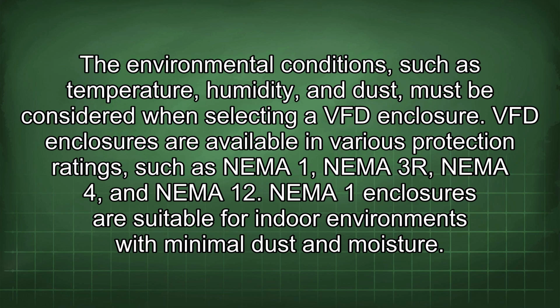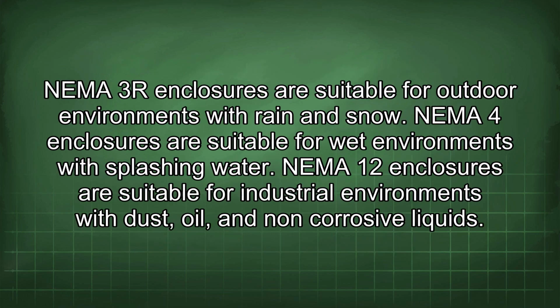VFD enclosures are available in various protection ratings such as NEMA 1, NEMA 3R, NEMA 4, and NEMA 12. NEMA 1 enclosures are suitable for indoor environments with minimal dust and moisture. NEMA 3R enclosures are suitable for outdoor environments with rain and snow. NEMA 4 enclosures are suitable for wet environments with splashing water. NEMA 12 enclosures are suitable for industrial environments with dust, oil, and non-corrosive liquids.